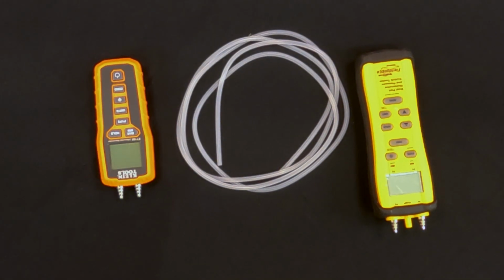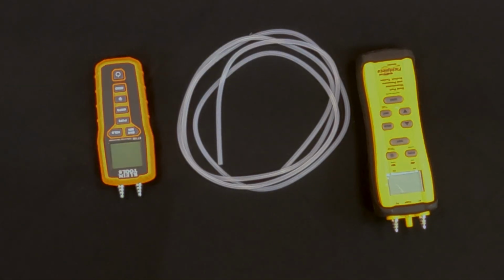Manometers. Again, there are a plethora of different styles and types on the market, digital and analog. A couple I have here just to give you an idea that it's more about what you're testing rather than the brand. This one is a dual port manometer, just like this one. This one has the additional feature of testing a pressure switch, which comes in handy if you're having issues with a pressure switch. But more to the point, a manometer checks your gas pressure in the heating system. Knowing your gas pressure and being able to adjust it is very important. These also work as a static pressure testing tool, and if airflow becomes an issue, you'll notice it more in heating season than cooling season due to high limits. Very important tool to keep in your bag and know how to use.